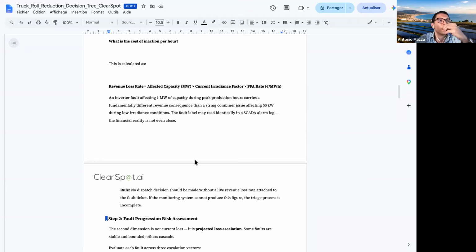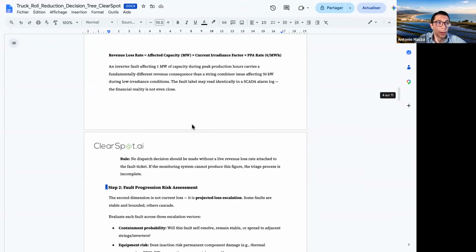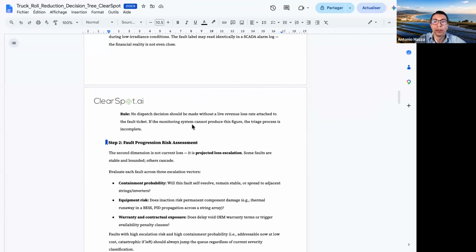So I will say this is really important. A dispatch decision shouldn't be made without a live revenue loss rate attached to the fault ticket. If you're running O&M across states, multiple departments, multiple areas, logistics is expensive and costly, teams are not available, and people are not that skilled with this issue. We know there is a huge gap in the industry of qualified personnel. The objective should be: can we run those numbers and prioritize based on the highest loss? This is really important, so you can start prioritizing based on how much you're losing rather than other conditions.